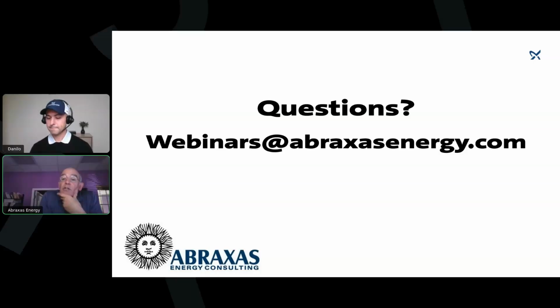Okay, here's one. Are you able to describe similarities or differences between the distributed pumping solution you described and using the Belimo energy valve or similar products? I think that's what it's called. I've heard of that product, but haven't gotten familiar with it. Yeah, so with energy valves, the idea is you're using throttle valves, right? So you're still having valve authority in your system. What happens with the energy valves is that they are more efficient than the mechanical valves. So you save energy by going from a mechanical valve to an energy valve, definitely, but you're still creating that pressure for the primary pumps, right?